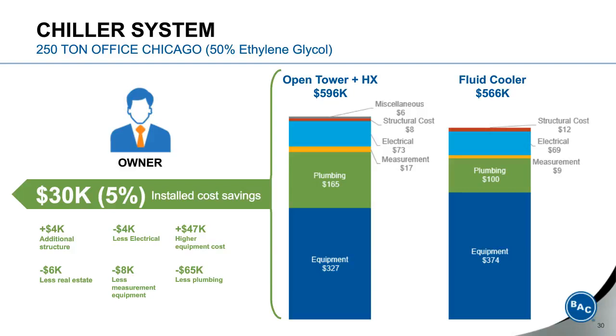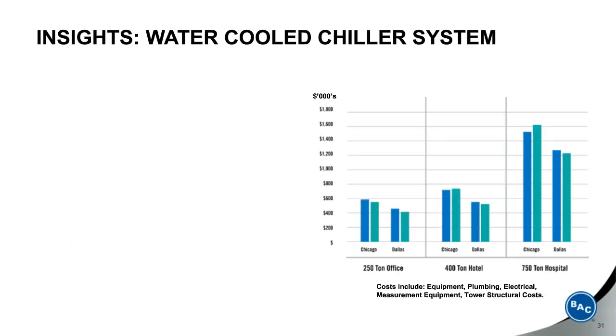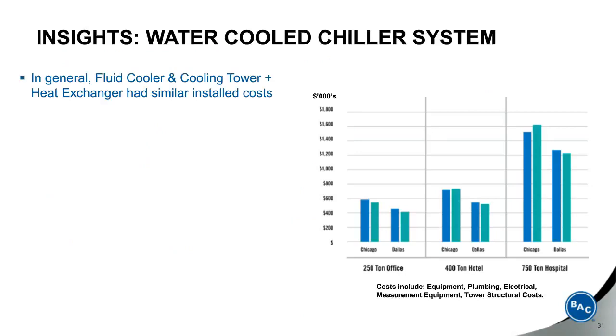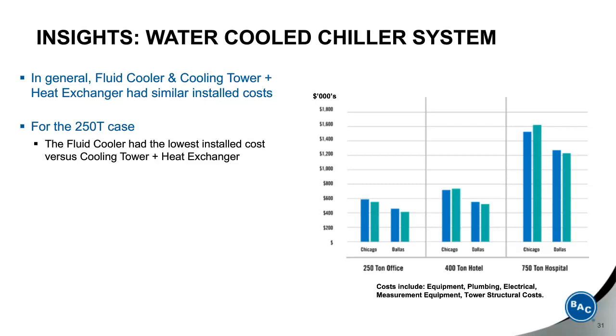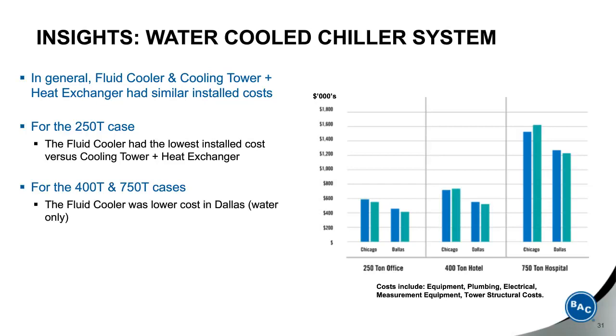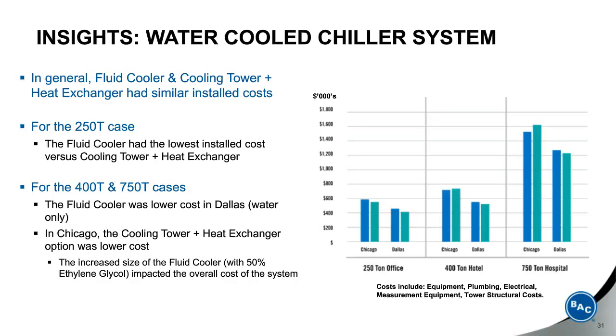Now this was based on a 50% ethylene glycol solution, which was chosen by our consulting engineers, IMEG, for this application. So looking at the insights that we've learned, in general, the fluid cooler and cooling tower heat exchanger had similar first costs. There were some factors that would throw the numbers one way or the other, but they were very similar. For the 250-ton case, the fluid cooler had the lowest installed cost versus cooling tower and heat exchanger. For the 400-ton and 750-ton cases, the fluid cooler was lower cost in Dallas, which is a water-only based system. In Chicago, the cooling tower and heat exchanger option were lower cost. The increased size of the fluid cooler due to the 50% ethylene glycol, along with the cost of the glycol in the system, impacted the overall cost of the system in this case.